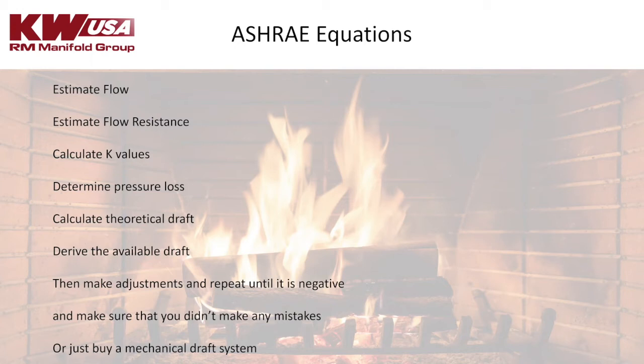It basically says that mass flow of flue gas in a vertical pipe is a function of heat release regulated by chimney area, height, and system pressure loss. But it doesn't consider a lot of things. It doesn't consider your location or crosswinds, and it assumes that everything is constant: all your heat input, your supply air, everything. You have a straight chimney. But in reality, we know that all those things are constantly changing. Draft is constantly changing. So even after you do all this math, all you have is a starting point, which is kind of where the art of venting comes in, which is using common sense and experience to understand and identify these potential draft problems you might have.